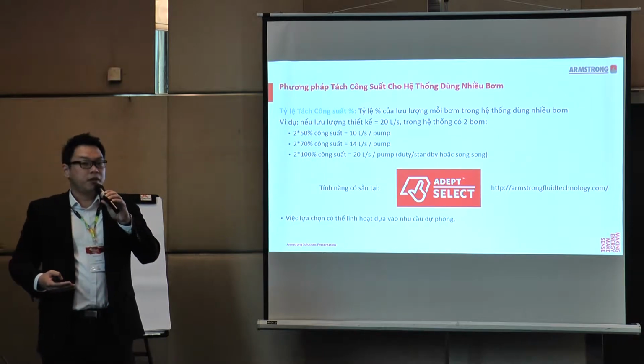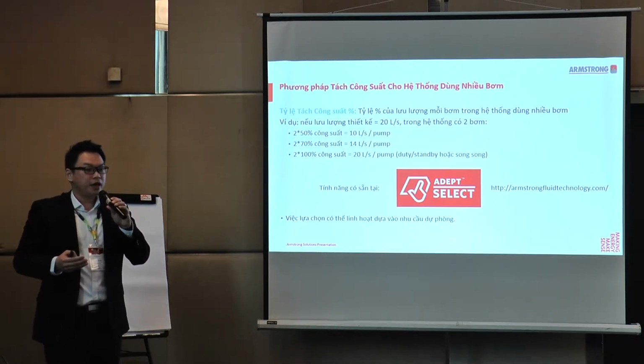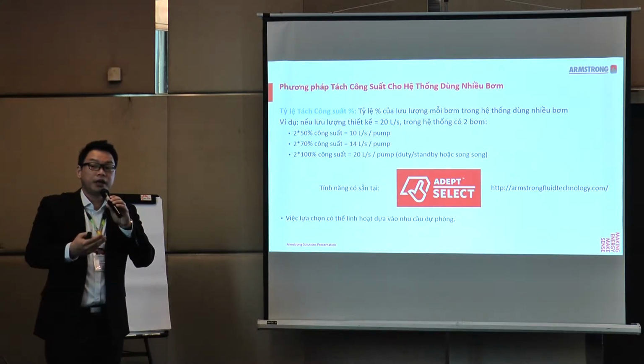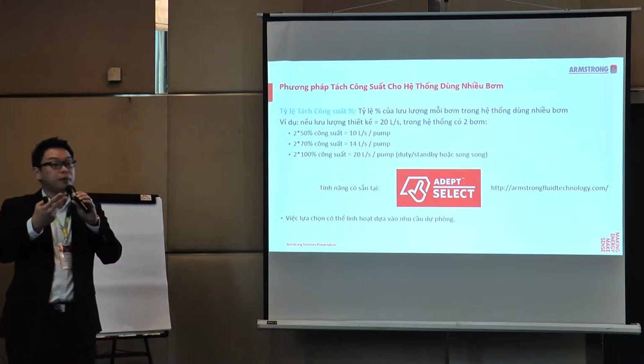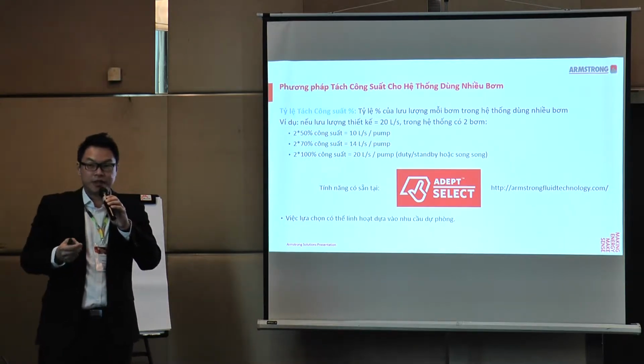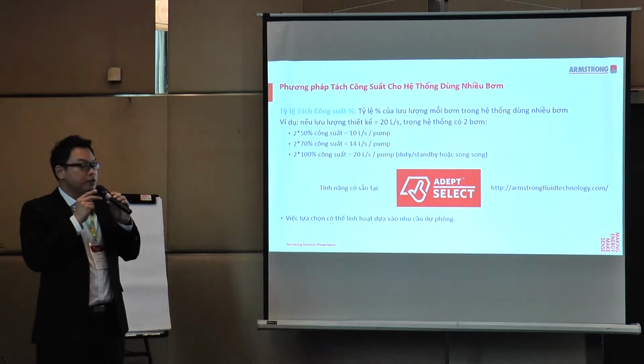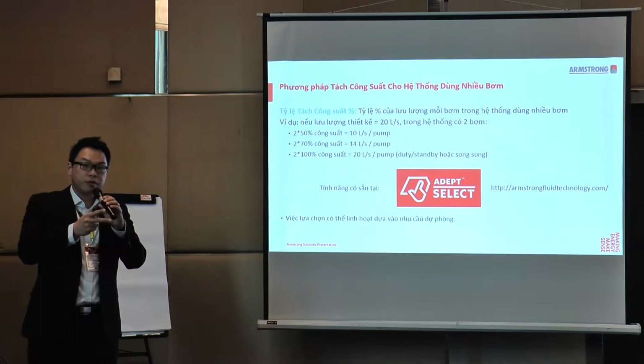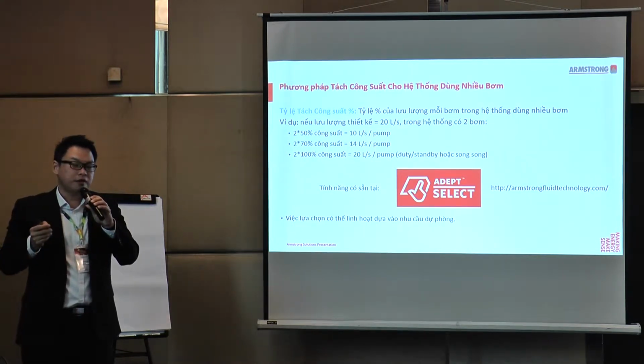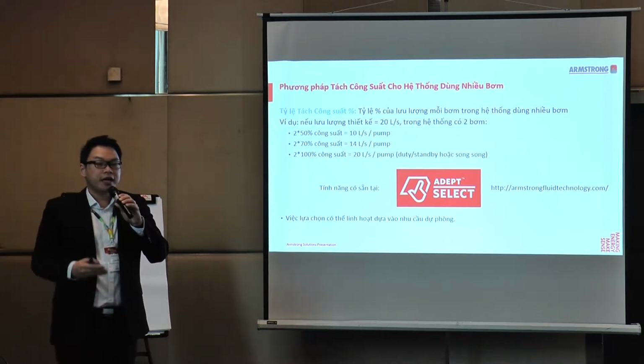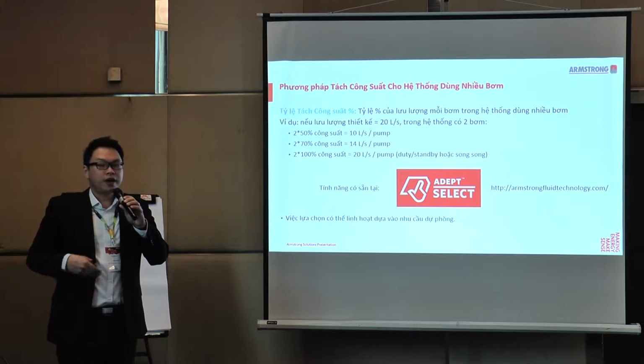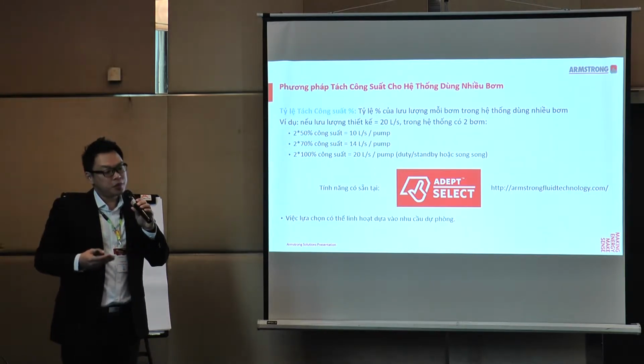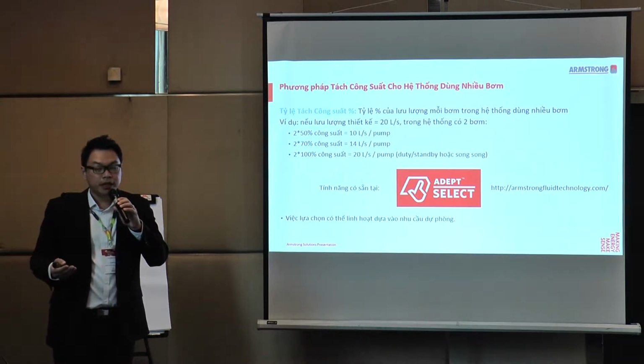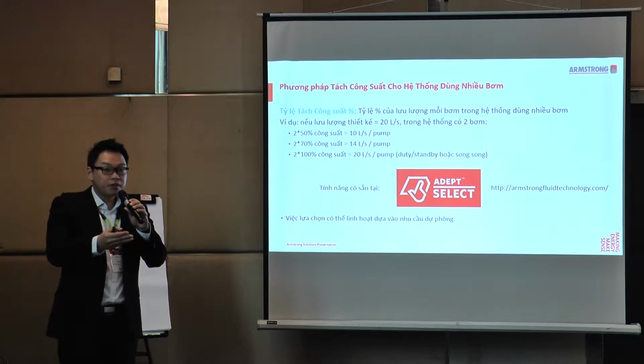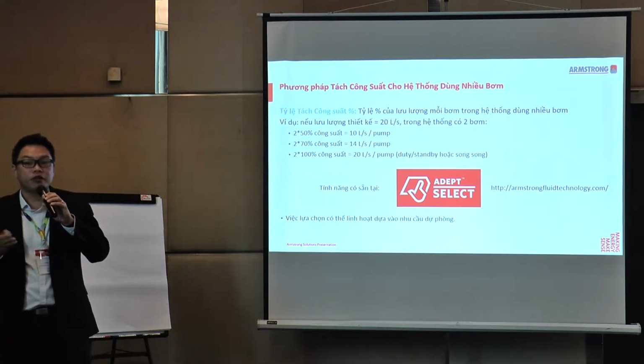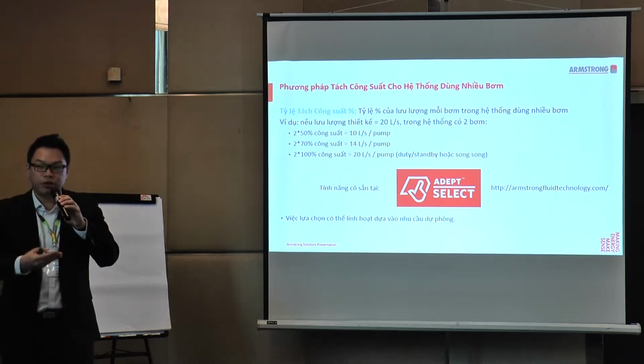A concept that I want to share with you is about capacity split, and this becomes useful when there is a multi-pump system. In this case, I'm going to consider two pumps with a design flow of 19 liters per second. If we consider a 50% capacity split with two pumps running, each pump will have 9.5 liters per second. If you have 2 times 70% capacity split, each pump will have 13.2 liters per second. And what if you size your pump for 2 by 100% capacity split? That means you have a duty standby configuration, or you can operate as a parallel operation.